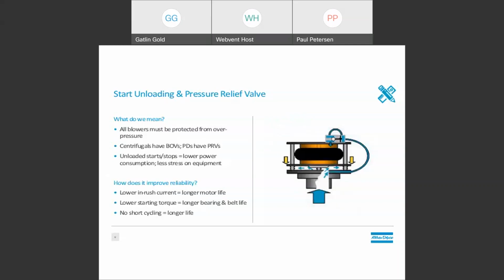Now, every blower should come equipped with a relief valve of some type. Centrifugal blowers typically come with a blow-off valve that prevents surge during startup and shutdown. This is required for them to start on a pressurized header or against a full tank. However, most PD blowers only come with a pressure relief valve because they're not subject to surge. The pressure relief valve protects equipment in case maximum allowable pressure is exceeded. However, it does nothing to protect the equipment from the stresses of startup and shutdown.